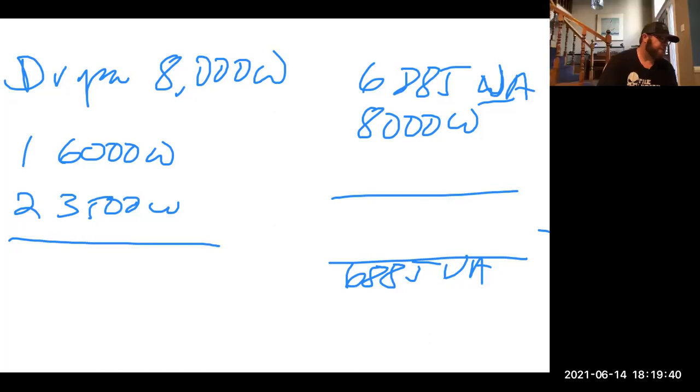That's right. So you told me originally 2 of them were 3,200 and one of them was like 6,000. Let's just say that's what they were. If there was a fourth one, you would just add that to whatever column they are. Now, if I had 3 of them that were a 6 and 2 35s, all 3 of those would be column B, because they're all 3,500 or larger up to 8.875. So I'm looking at row 3 then in column B, which is going to be 55%, is it? Yeah, 55. So you add them up, but only to just make the math easy. So it's 7 and 6, 13, 13.5, is it?